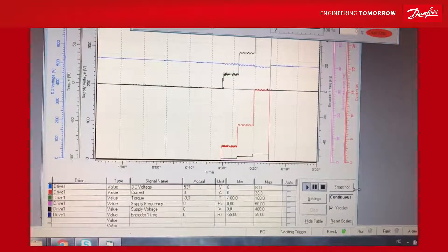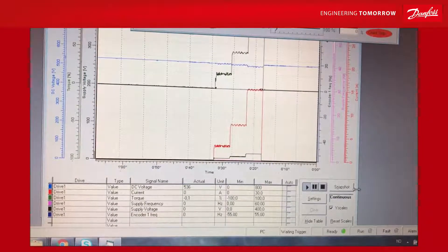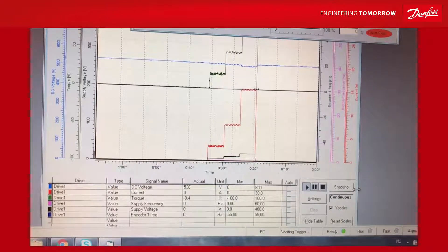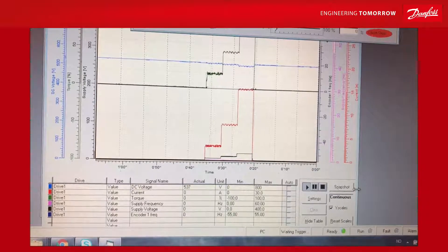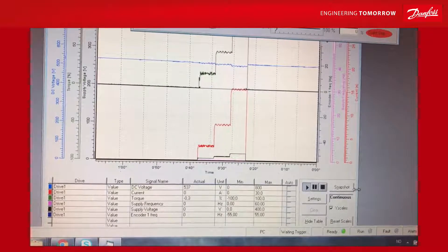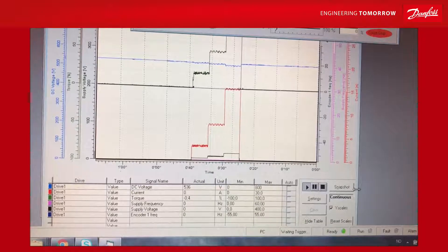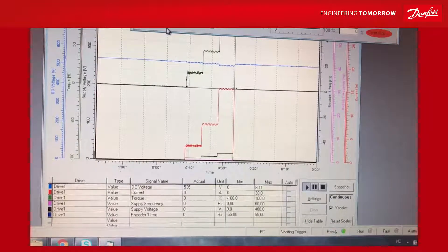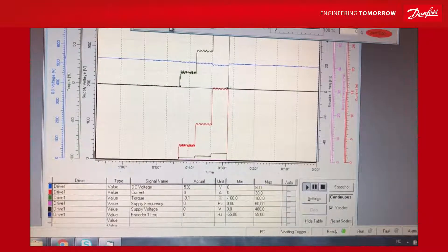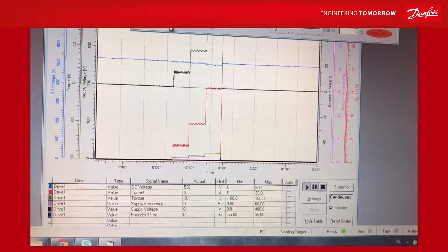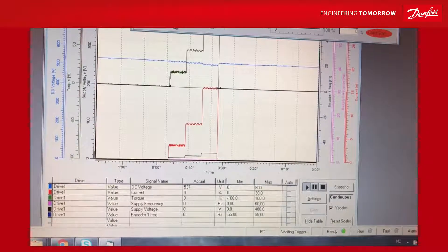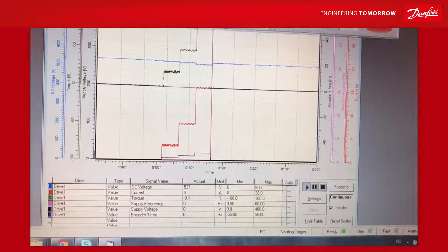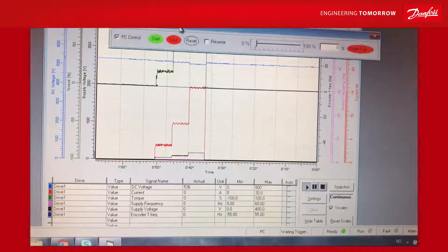The next step will be identification with rotation. But first I want to check that this motor can run freely and nicely. Here comes a startup in open loop, which means that the polar angle is not identified, so it could be a little bit brutal. Let's see what happens when I try to start it.